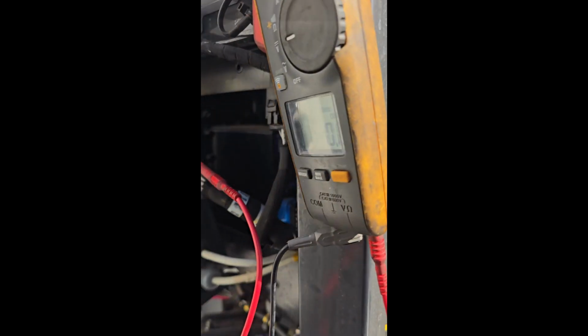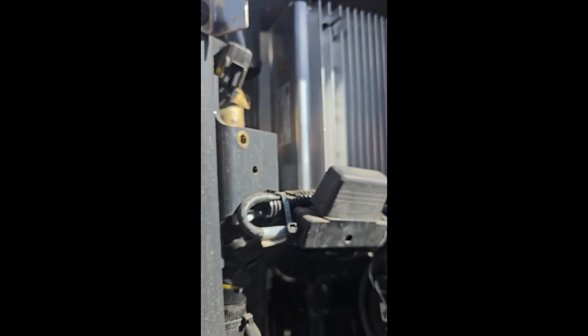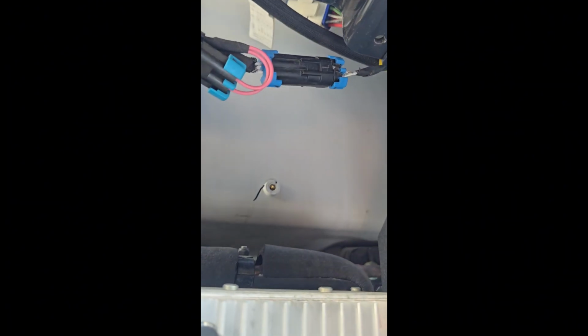So that means between here and up here where the white plug is, we may not have a connection, because we don't have nothing coming from pin 31 all the way over to the box over there. Okay, so I'm going to go ahead and unplug that, and we're going to check for voltage at the condenser fan motor plug there. Be back.